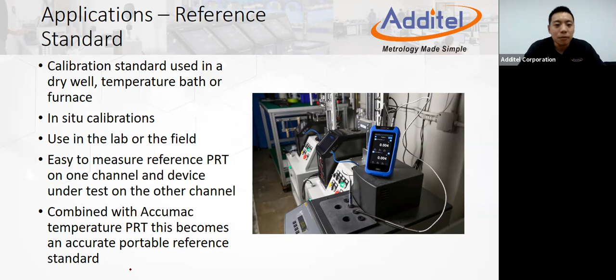So anyway, about other applications, we can use the 282 for some industrial uses, like freezer verifications or production line verifications or temperature data logging or chamber verification or testing or something like that. Because it has 2 channels, you can easily use it to do a 1-point calibration or testing or verification or monitoring, or 2-point monitoring and measure the temperature difference between these 2 points.